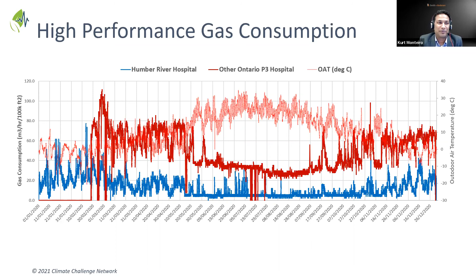We've replicated that in just about every project since, even applying it to retrofit work, increasing sizing instead of following the traditional model, since this is a healthcare facility running 24/7 with higher air changes per hour. In those cases we oversize the air handling units and ductwork where possible, even in existing areas, because we know there are real savings, as we've seen here. That's one big thing.